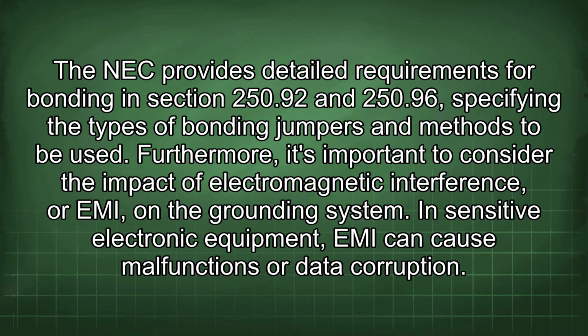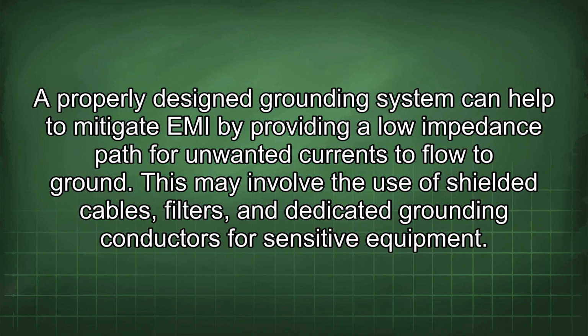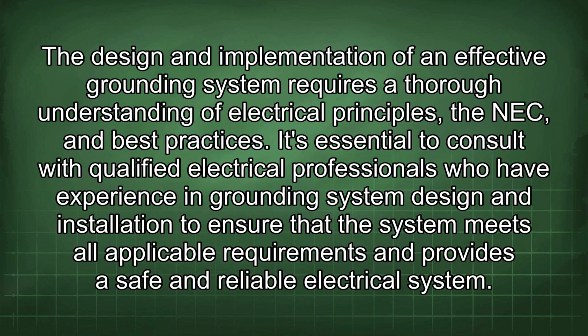Furthermore, it's important to consider the impact of electromagnetic interference, or EMI, on the grounding system. In sensitive electronic equipment, EMI can cause malfunctions or data corruption. A properly designed grounding system can help to mitigate EMI by providing a low impedance path for unwanted currents to flow to ground. This may involve the use of shielded cables, filters, and dedicated grounding conductors for sensitive equipment. The design and implementation of an effective grounding system requires a thorough understanding of electrical principles, the NEC, and best practices.